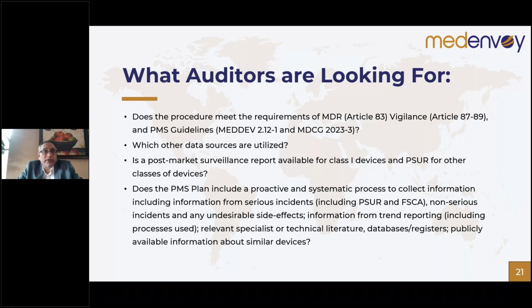All the products, for example, if you have a class 1 product as well as other classes, the auditing organization will be looking at whether you have generated a class 1 post-market surveillance report or not, even though they are not auditing your product as a notified body. From a process point of view, they will ask and check whether you have generated a PMS report as per your procedure for your class 1 devices.